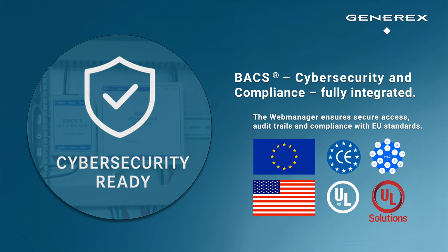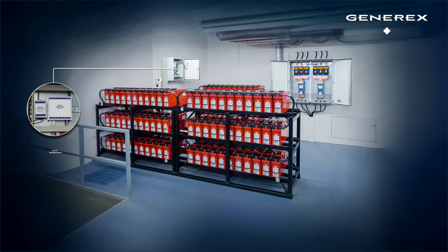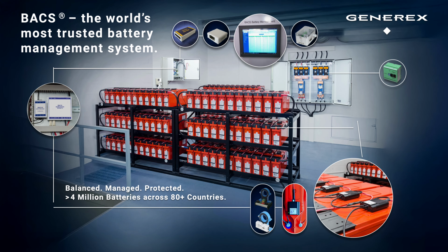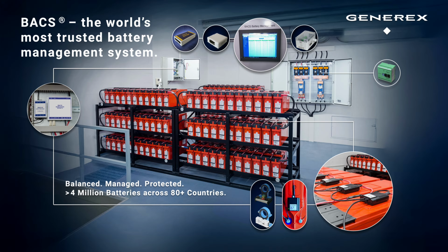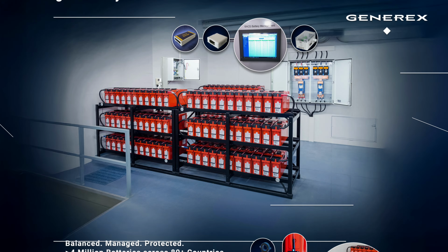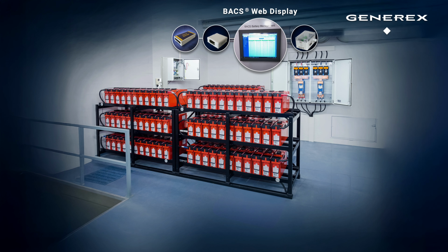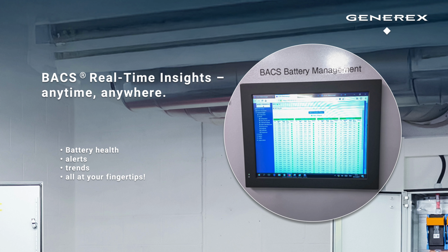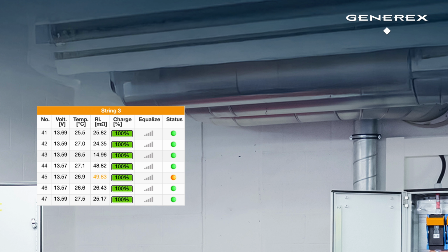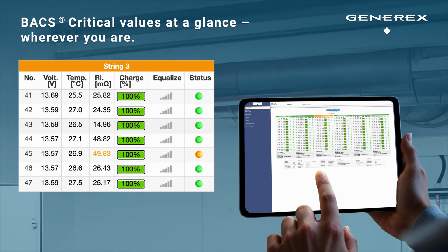The BACS CC cabinet is also available with a built-in monitor for observing measurement values from outside the cabinet and is also available featuring a full-fledged Windows PC with touch panel. The BACS main screen displays every battery with its corresponding number and the current voltage, temperature, and internal resistance. From this, the battery capacity is calculated, and the BACS Web Manager decides whether Equalize, the balancing of the voltages, is activated. In this example, the internal resistance of battery 45 is above the warning limit and should be investigated.